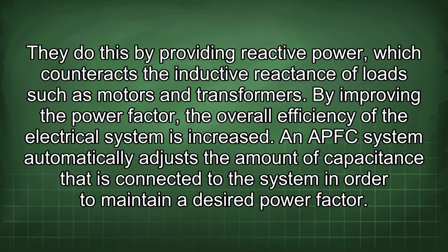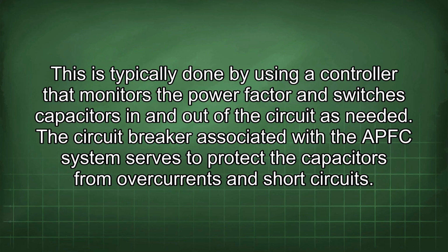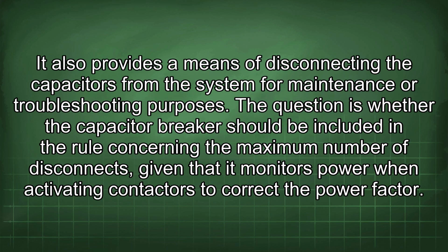An APFC system automatically adjusts the amount of capacitance that is connected to the system in order to maintain a desired power factor. This is typically done by using a controller that monitors the power factor and switches capacitors in and out of the circuit as needed. The circuit breaker associated with the APFC system serves to protect the capacitors from overcurrents and short circuits. It also provides a means of disconnecting the capacitors from the system for maintenance or troubleshooting purposes. The question is whether the capacitor breaker should be included in the rule concerning the maximum number of disconnects, given that it monitors power when activating contactors to correct the power factor.